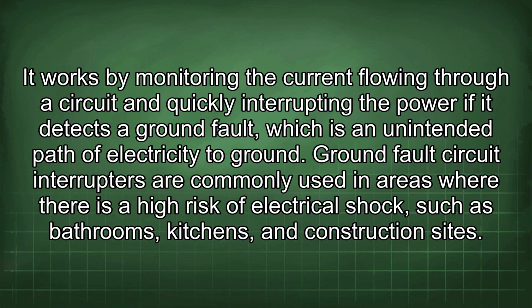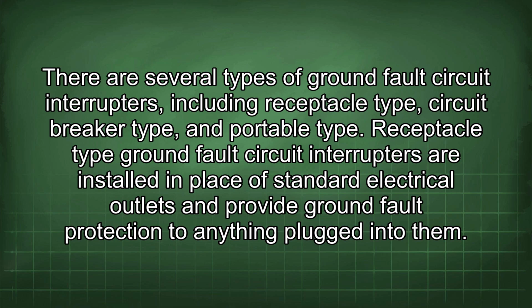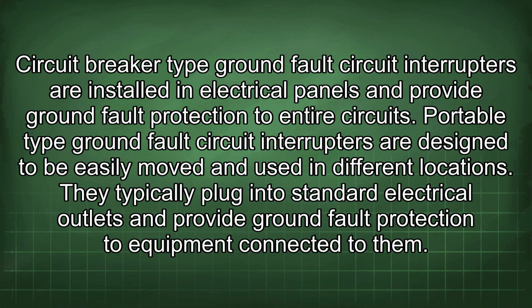Ground fault circuit interrupters are commonly used in areas where there is a high risk of electrical shock, such as bathrooms, kitchens, and construction sites. There are several types of ground fault circuit interrupters, including receptacle type, circuit breaker type, and portable type. Receptacle type ground fault circuit interrupters are installed in place of standard electrical outlets and provide ground fault protection to anything plugged into them. Circuit breaker type ground fault circuit interrupters are installed in electrical panels and provide ground fault protection to entire circuits. Portable type ground fault circuit interrupters are designed to be easily moved and used in different locations. They typically plug into standard electrical outlets and provide ground fault protection to equipment connected to them.